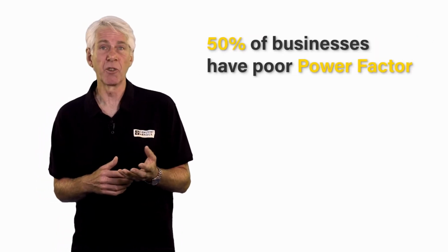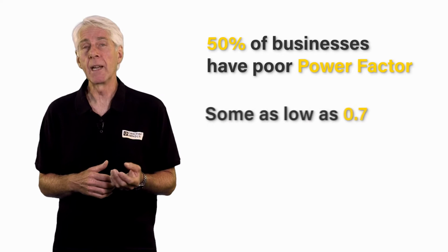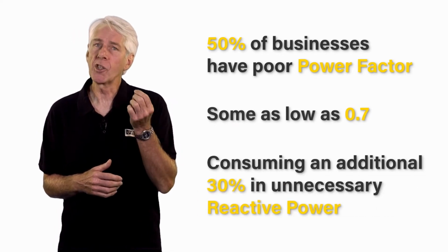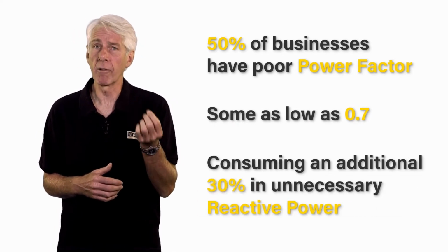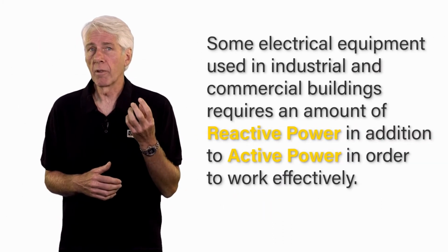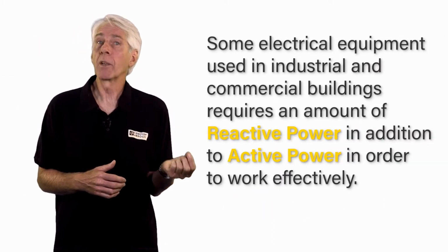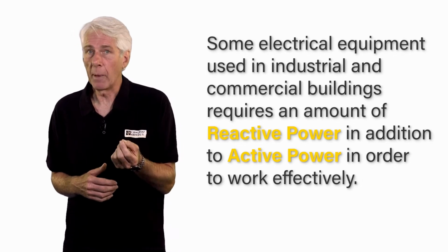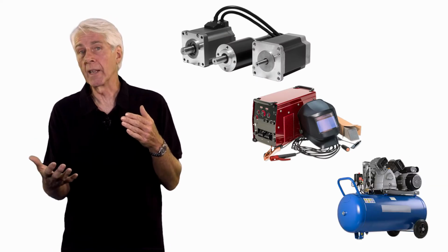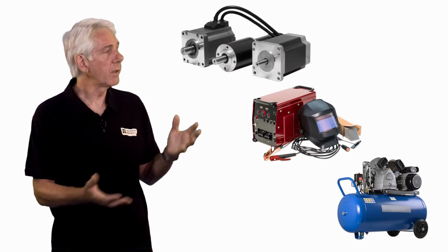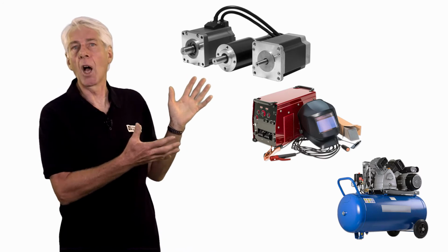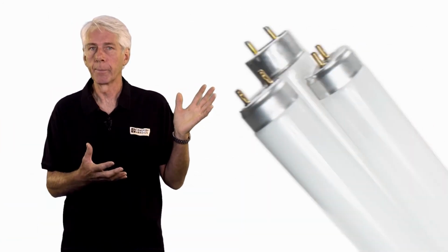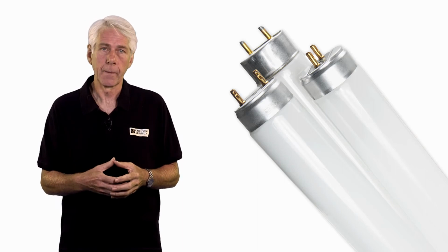Disappointingly, 50% of businesses have poor power factor, many as low as 0.7, consuming an additional 30% in unnecessary reactive power. Now, if you don't already know, some electrical equipment requires an amount of reactive power in addition to active power in order to work effectively. These tend to be items with copper windings in them, especially transformers, motors, induction heaters, arc welders, compressors and the like, even fluorescent lighting. Now, it gets a little complicated. Stay with me, we may need beer.